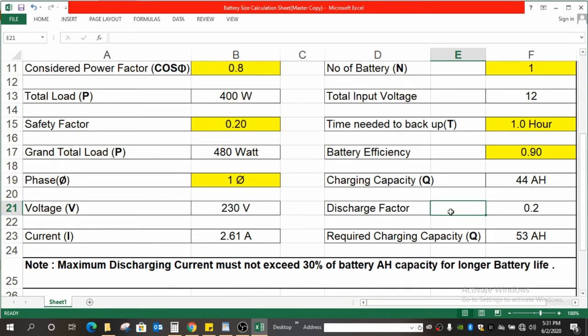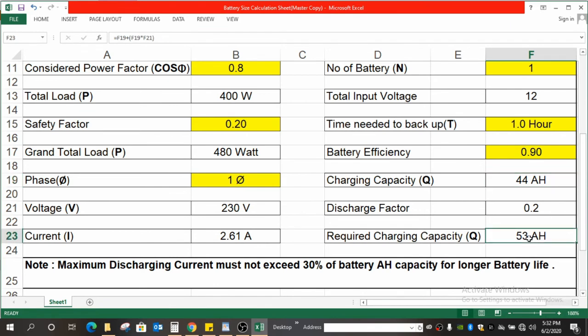In that case, I have considered 0.2 as a discharge factor. If you are not considering 0.2, then the total charging capacity, the total capacity of battery, will be 44 Ah. If you are considering it, then that will be 53 Ah. It is the requirement for our project.